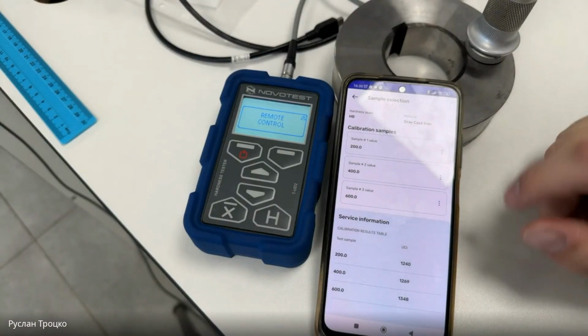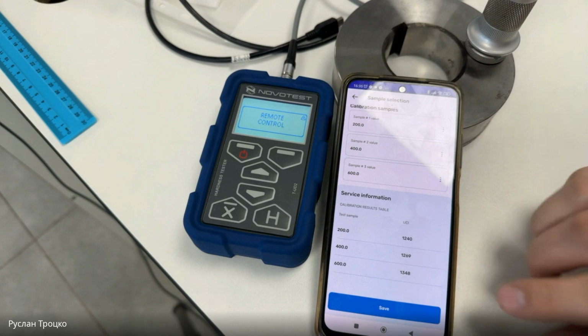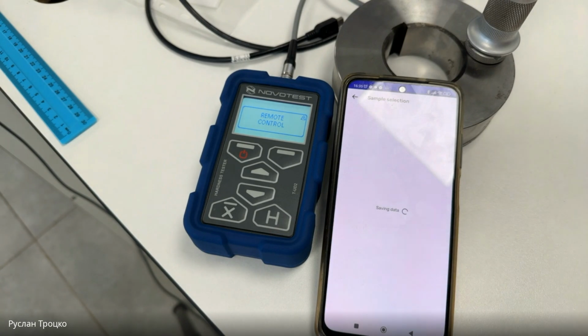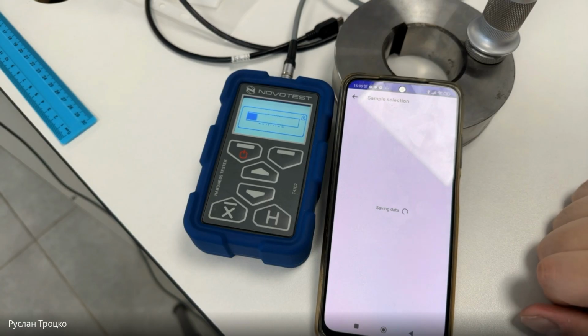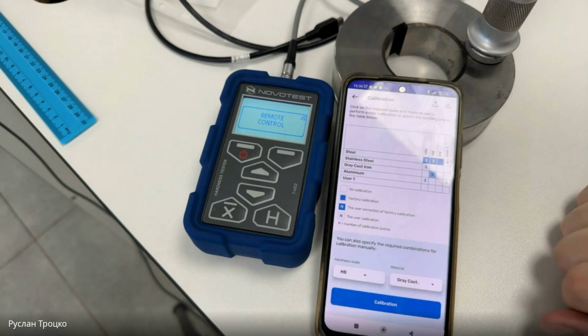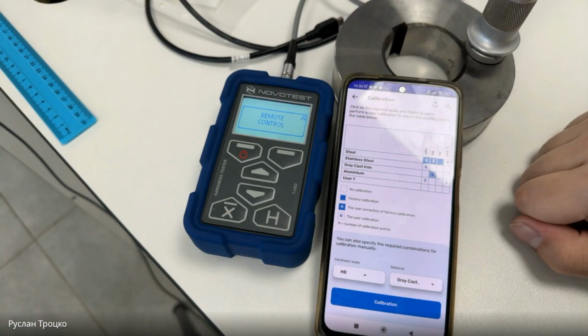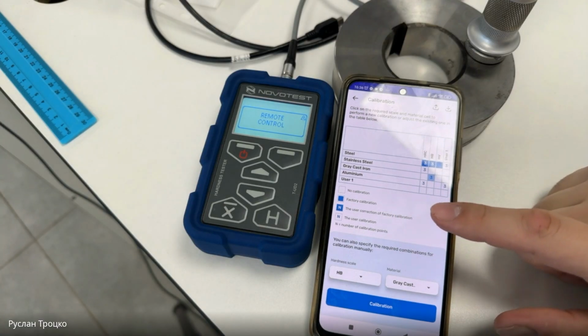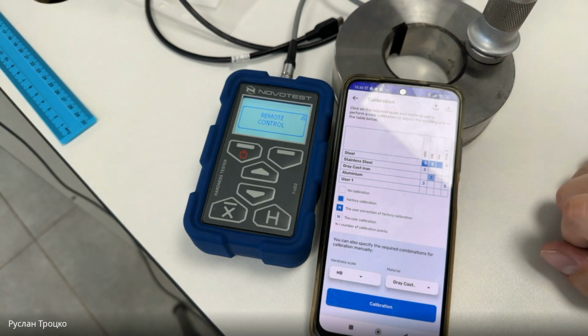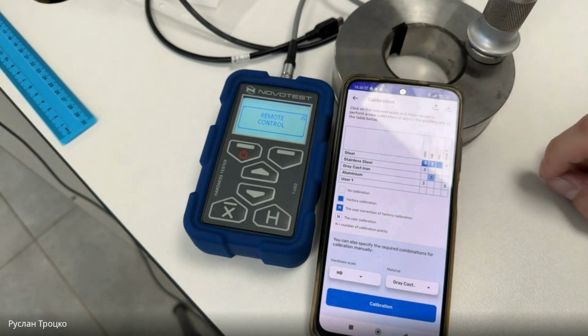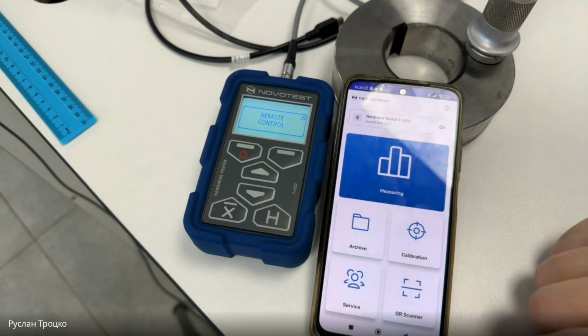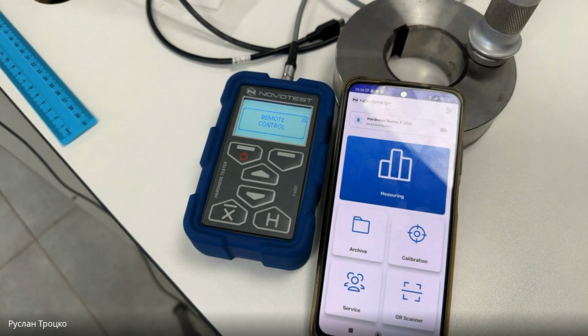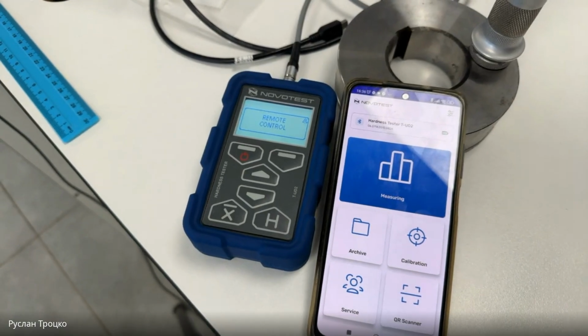Okay, complete calibration. You see, I have results for 3 of my samples. I click save, and the calibration is saved. Here it is. I created a calibration for gray cast iron for the HB Brinell scale. So the same works in the device.